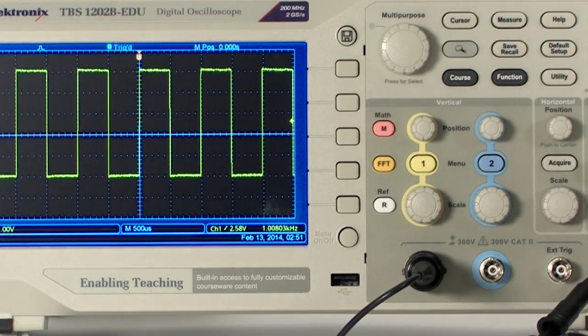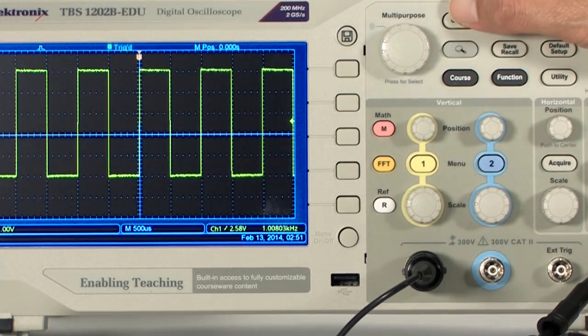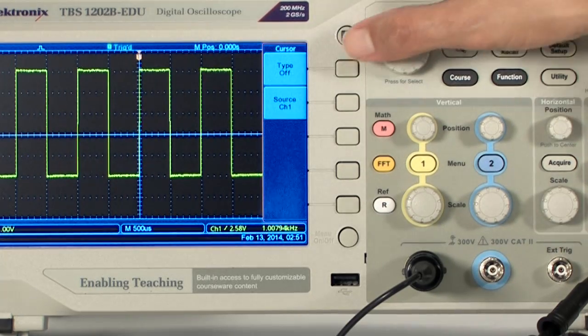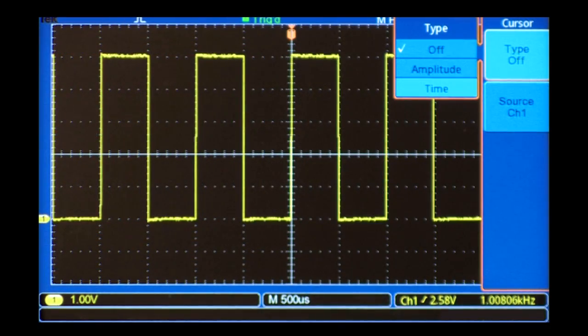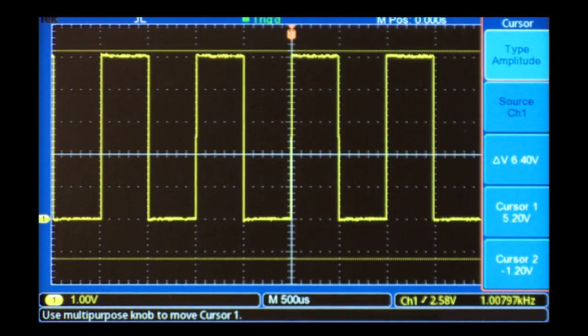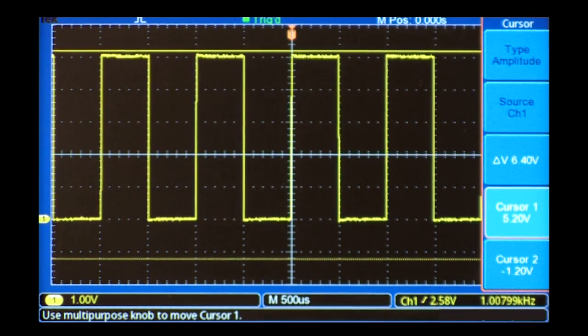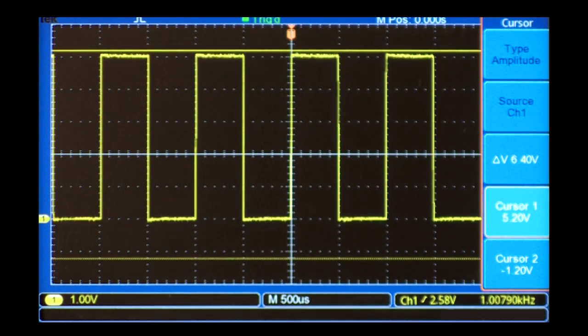Cursors can also be used to make voltage and time-related measurements. They incorporate the scale settings to read out directly in volts and seconds. To measure voltage, set the measurement type to amplitude. This brings up two horizontal cursors. Since the signal is connected to channel 1, I need to make sure that it's the source for the cursor measurement.